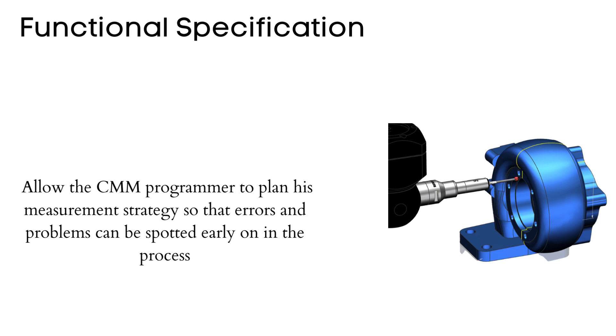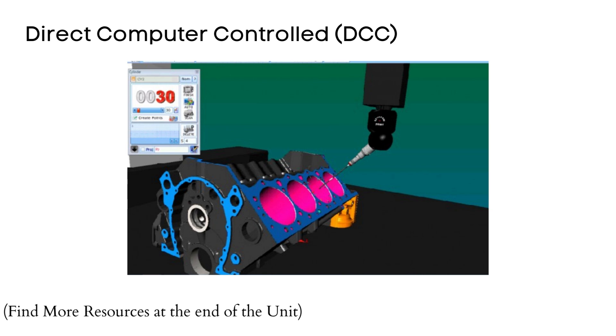The purpose of the functional specification is to allow the CMM programmer to plan his measurement strategy so that errors and problems can be spotted early on in the process. Many software packages contain an automatic feature measurement function that allows the CMM to automatically move to a defined feature and take measurement points on it, facilitating the creation of a direct computer-controlled program.